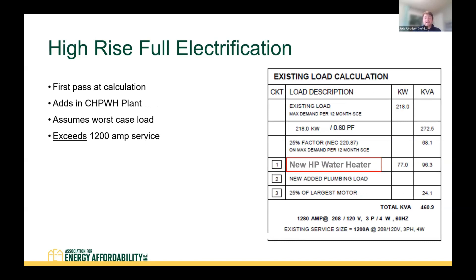Taking those 254 amps of available capacity, the question was: can we electrify the water heating and space heating? The answer was initially no. Adding a new central heat pump water heater plant to the existing load would result in 1,280 amps of required service — exceeding the 1200 amp service and triggering a service upgrade. For a 199-unit building, that almost certainly triggers transformer upgrades and costly utility-side upgrades at the owner's cost, so we really needed to avoid that.